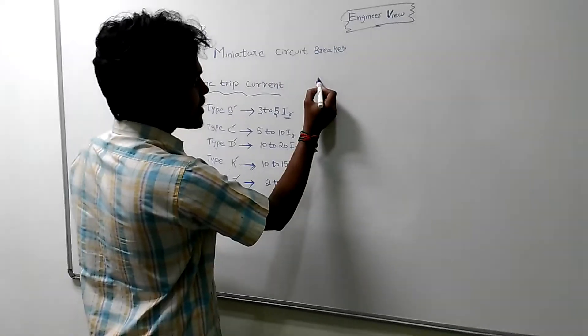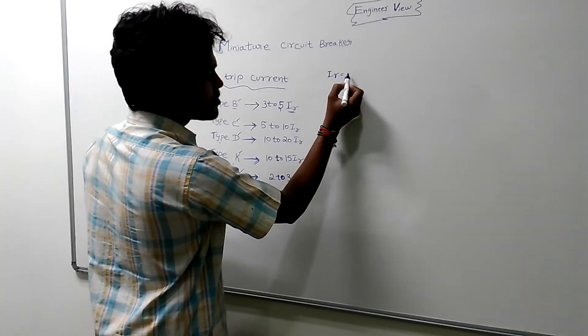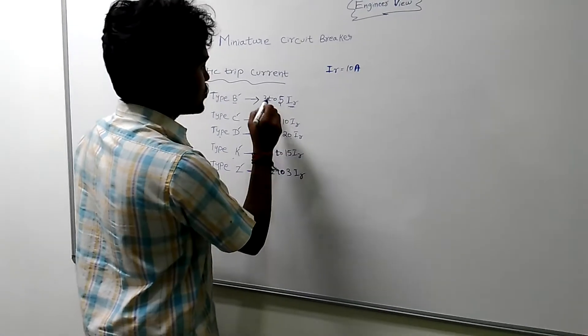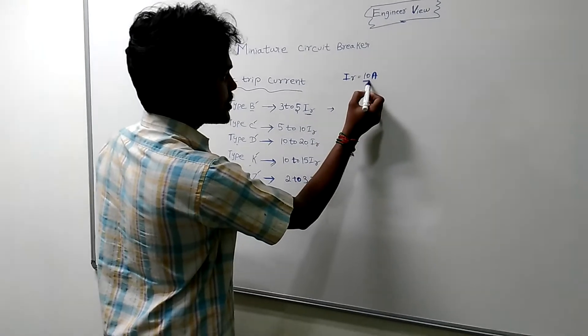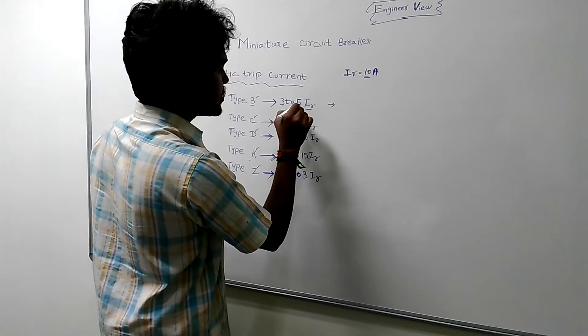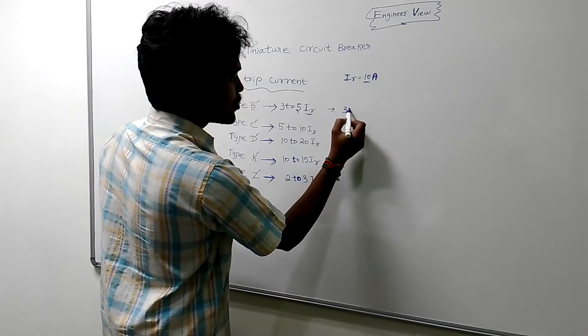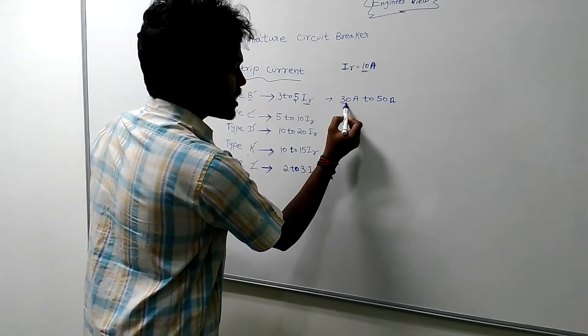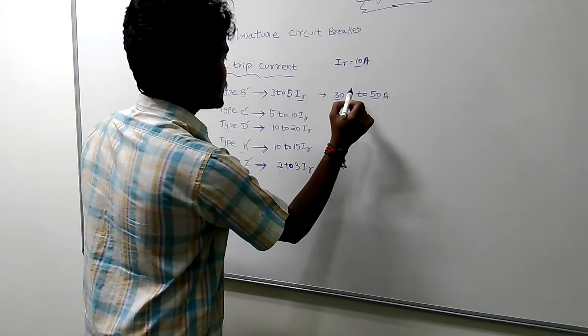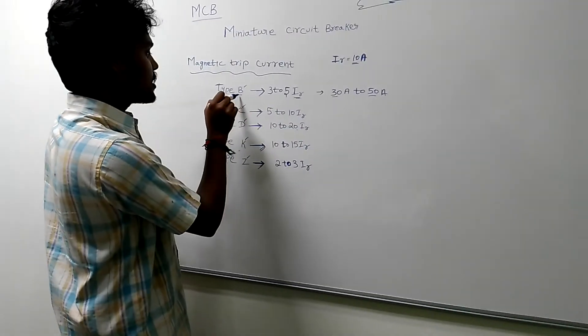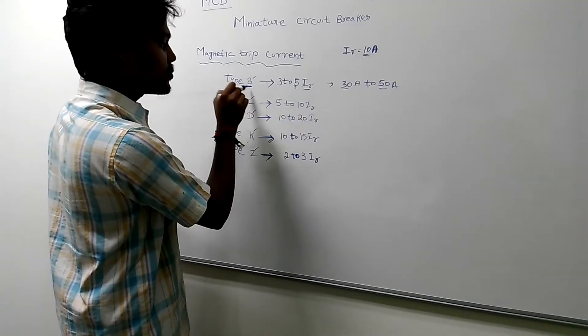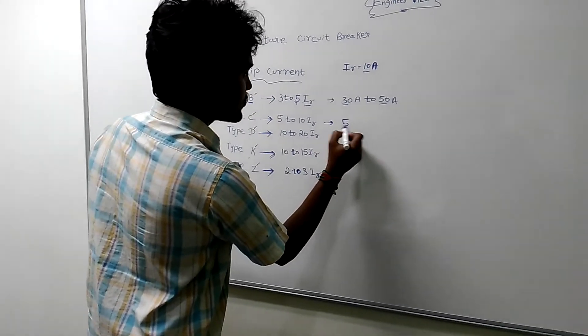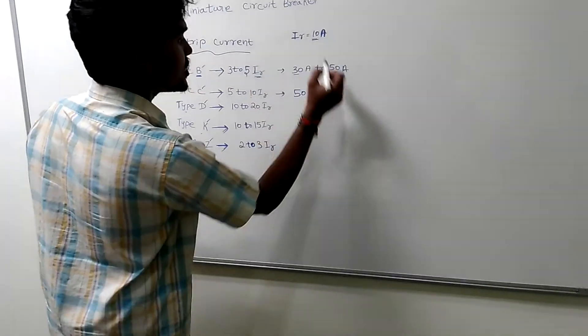For example, if the rated current is 10 amps, for Type B — which is 3 to 5 times the rated current — the trip range will be 30 amps to 50 amps. So the range is from 30 amps up to 50 amps.